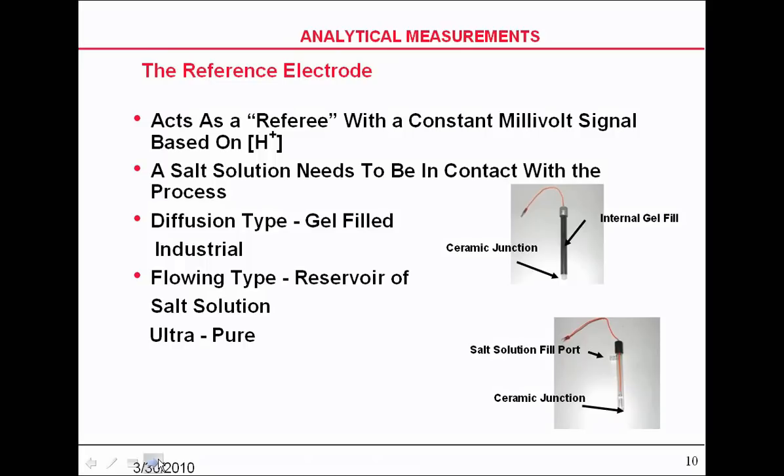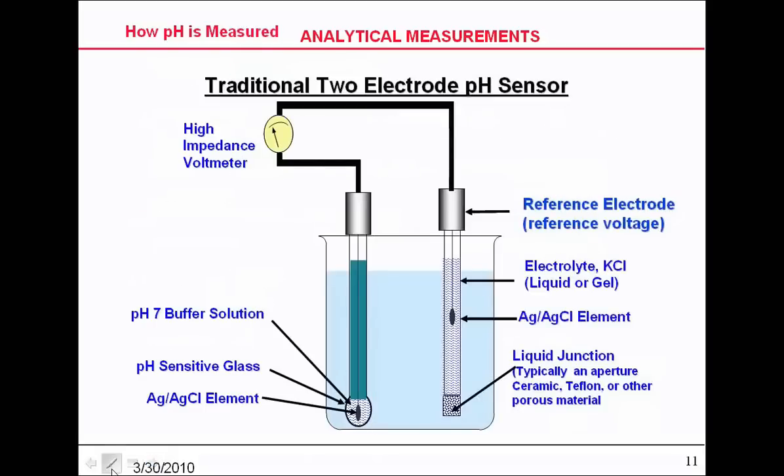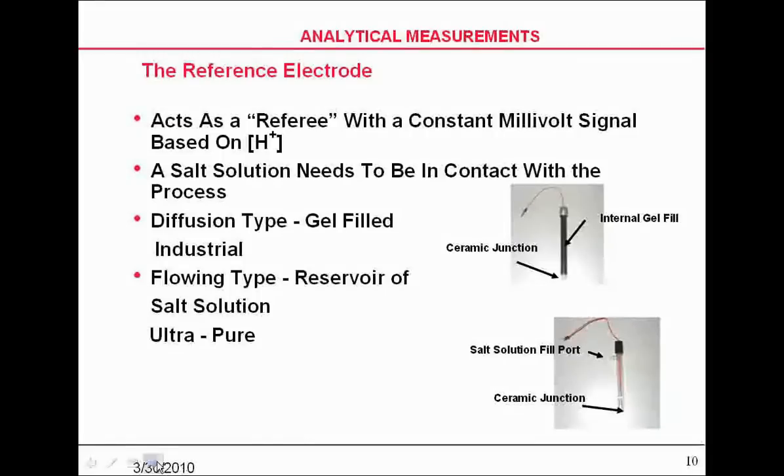When we're talking about the ultra-pure, which is the electrode on the bottom, we like to use the flowing type, and in that case, it's a one-mole type KCl. There are industrial types for process, and it's good to know that you basically use two different reference solutions for two different applications.